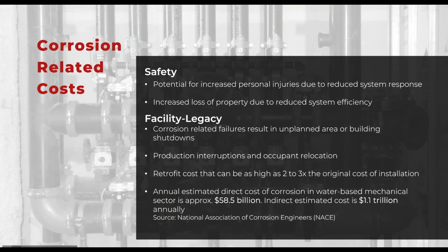And all of this is cost. So there's safety cost, there's monitoring. You may have to have a fire watch if you have a corrosion related issue on your system. There's pipe replacement costs, there's downtime, there's tenant interruption, there could possibly be an insurance claim if there's water damage issues. All of these things are costs. One of the large big box retailers actually now tracks the cost of corrosion in their publicly available 10K reports. They have the cost of service and repair on life safety systems, and that's code speak for corrosion related problems.